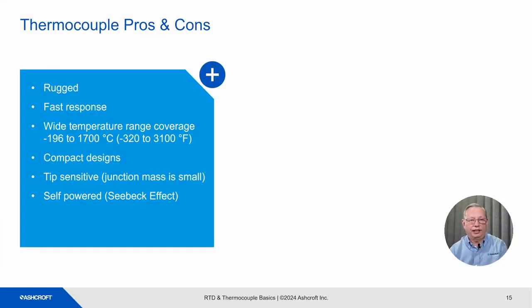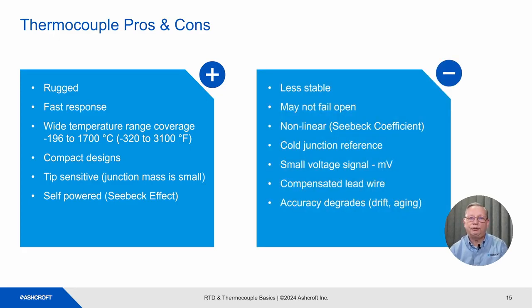Thermocouple pros and cons. The pros are very rugged design. They have a fast response time, especially grounded junctions. A very wide temperature range. They can be very compact. They are tip sensitive. They are self-powered. The cons are thermocouples are less stable than RTDs. They may not fail open. Often they will drift out of specification. They are nonlinear. They need a cold junction reference. They have a small millivolt output signal. You must use compensated lead wire to connect them to transmitters. The accuracy of them degrades over time.